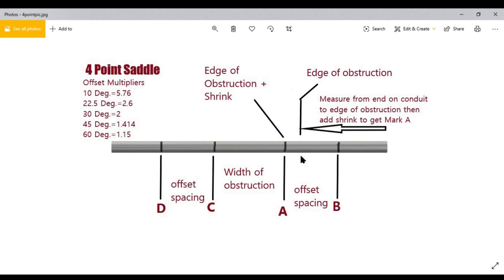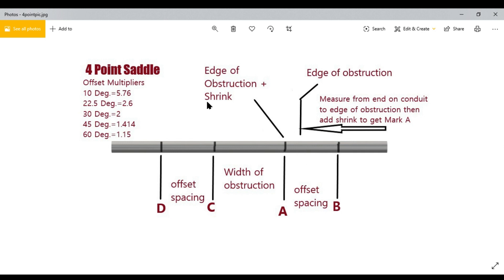Before you go and lay this conduit out, you want to figure out what degree of bend you want to use for the saddle — whether it be 30, 45, or 22 and a half degrees. You want to calculate the offset spacing, and then calculate the shrink. You're going to need all that to lay it out.